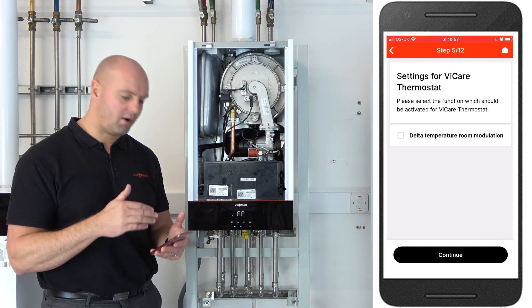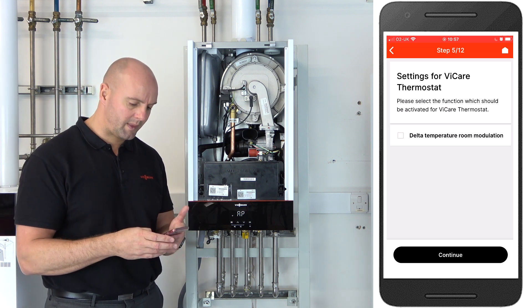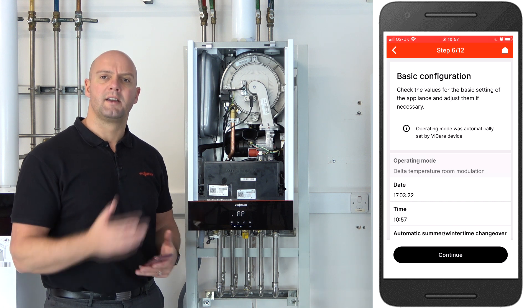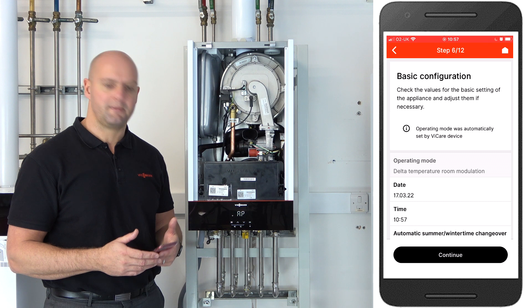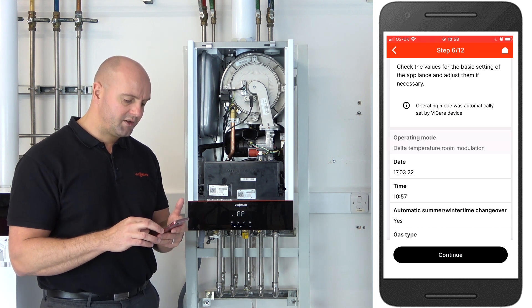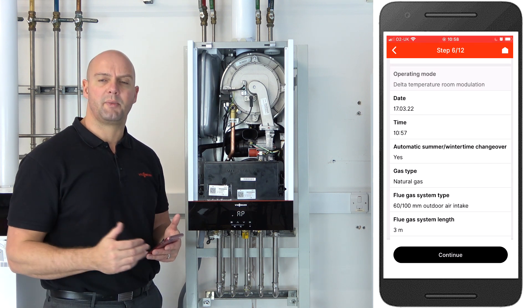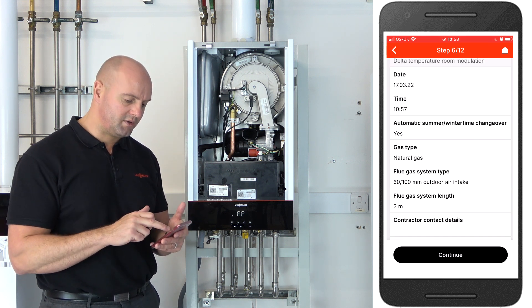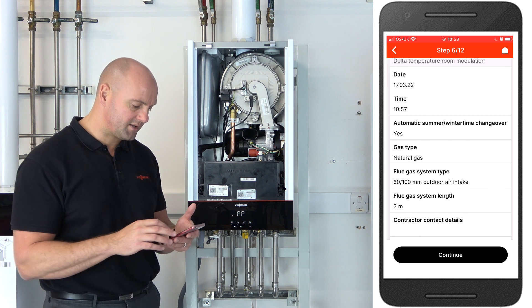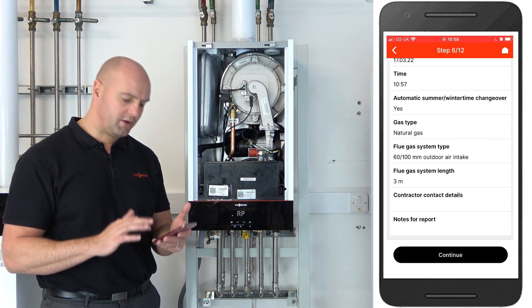The next step: we have to tick the box that says 'delta temperature room modulation' because we're adding a ViCare thermostat today. Click continue — it then comes up with the configuration for that heating circuit. The ViCare thermostat can only run one heating circuit, so a lot of this is pre-populated. In the operating mode it's already set to delta temperature room modulation. You can check the date and time, and set the automatic changeover for summer and winter time to yes. If you want to put this on an LPG system, click on gas type and change it to LPG — there's no need for restrictor discs or gas valve changes. You can also change the flue length or flue type depending on your installation, then click continue.